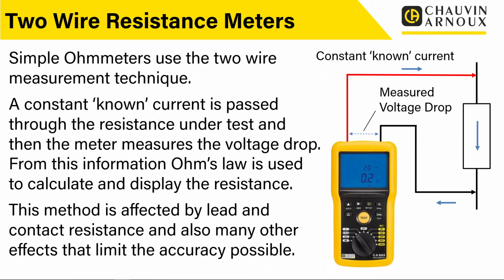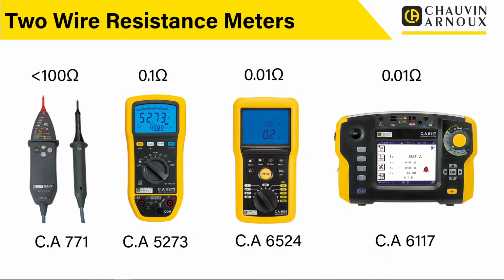So because of the method that's used, and things like lead resistance and contact resistance and all the other factors we'll talk about later in this webinar, there is a limit to the accuracy that you're going to achieve with a 2-wire measurement. So if we just look at typical 2-wire test instruments, on the left hand side there the 771, we talked about that, that's accurate down to below 100 ohms, somewhere in that category. And we said really that probably wasn't even a resistance measurement, it's more of a continuity measurement.